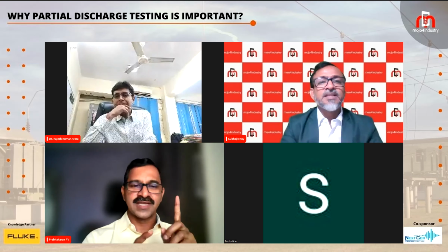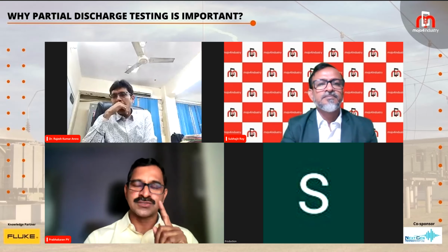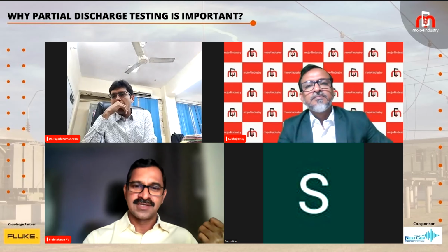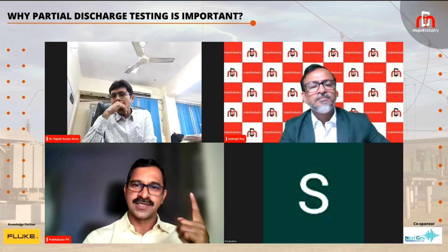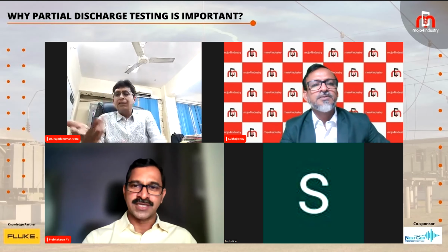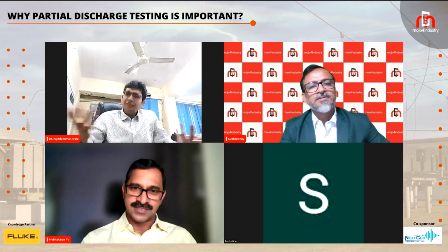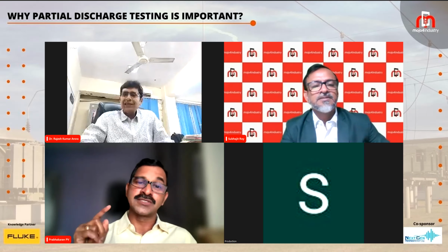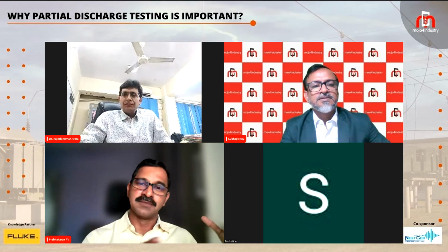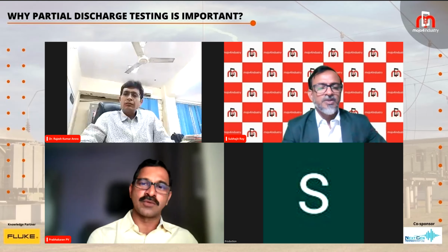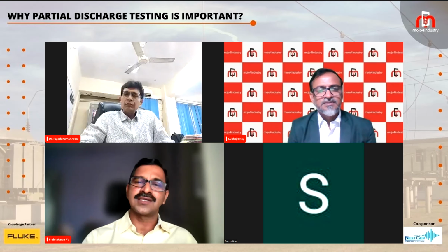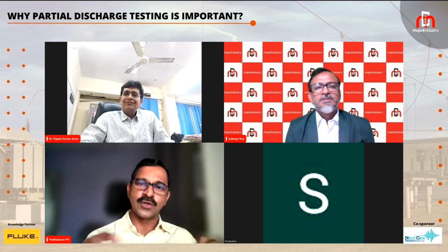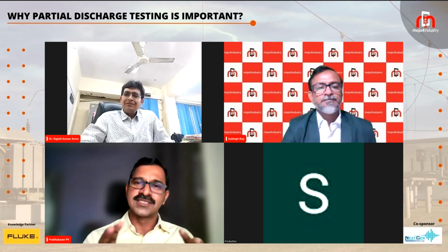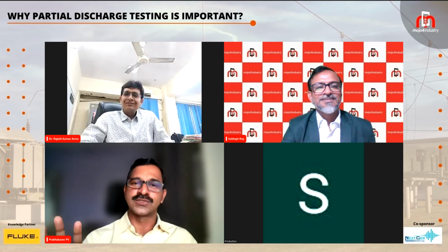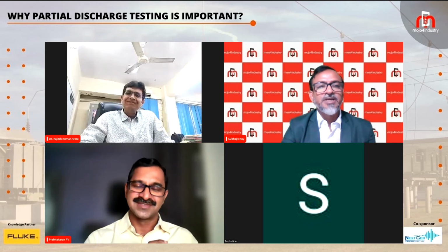Okay, and any threshold? It again depends, because as I mentioned earlier, the partial discharge failure can take 1 hour, a few seconds, a year, or even many years. It depends on various things - the material strength, the environment, the electrical stress, the environmental stress, or mechanical stress - many things are there. That's why one medicine is not there for every partial discharge. This is a tricky question, and there is no simple answer for that - and there's also a question about any threshold limit of PD.